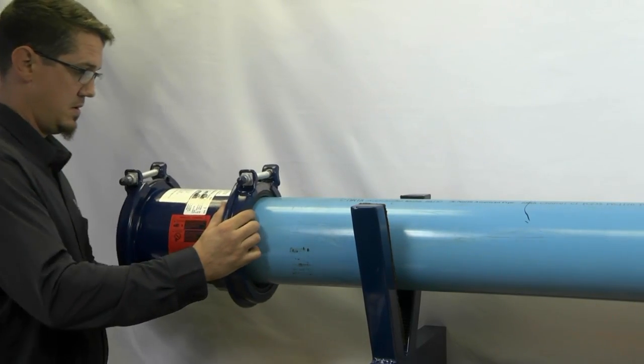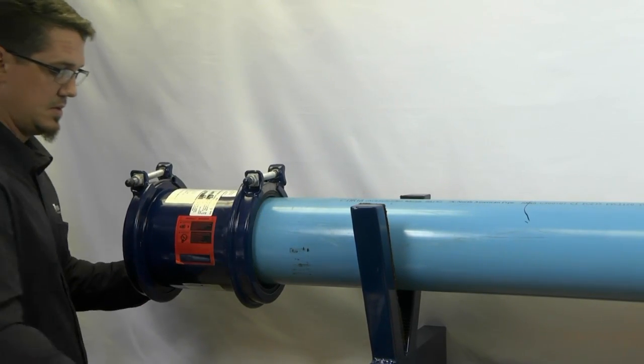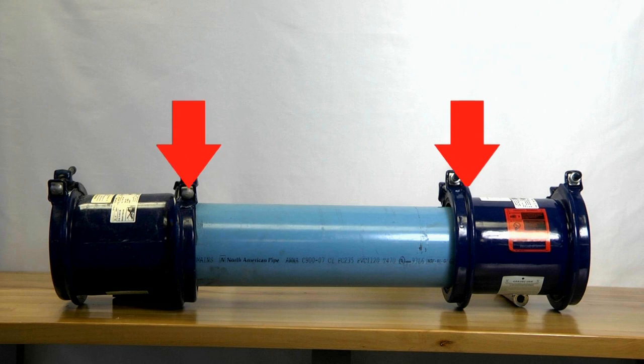Position the coupling for the installation. Make sure the bolts are on the top. If possible, place a coupling on each end of the pipe before lowering into place.